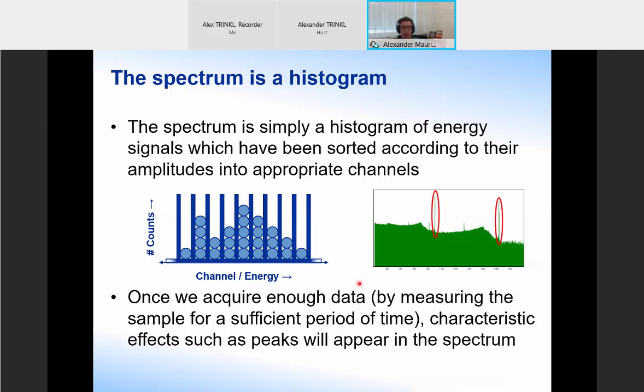Summarizing this whole signal processing as an example, we have a source or sample that emits a gamma ray. We get an electrical signal out because of the high voltage we put over our detector. It might go through the preamplifier, creating a pulse there, then be sent to the main amplifier, which creates a pulse with a much nicer shape, converted from analog to digital by our ADC, then sorted by our multi-channel analyzer, eventually into a spectrum.